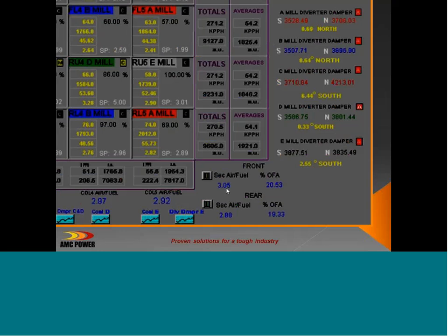So if we have an average air-to-fuel ratio and all the burners operated at that average, we have good combustion. So that average becomes the set point. So on the front wall, for instance, we know how much fuel from the feeders and how much air from the secondary air duct is going to that wind box. That becomes a set point.